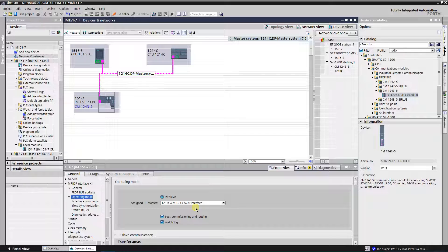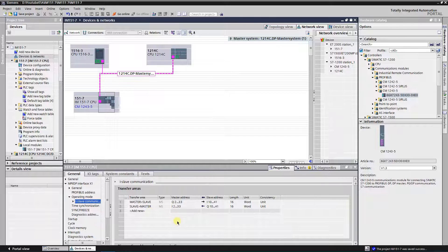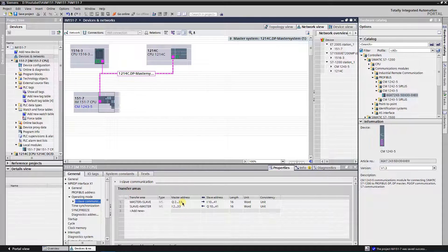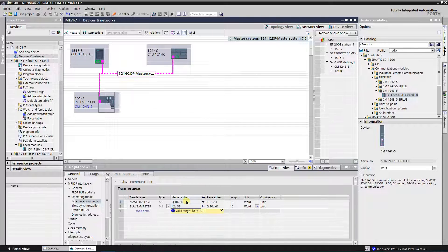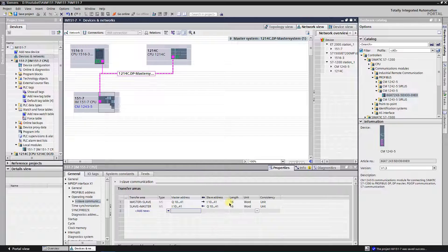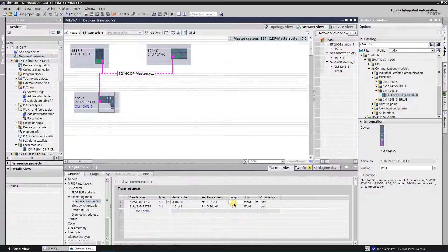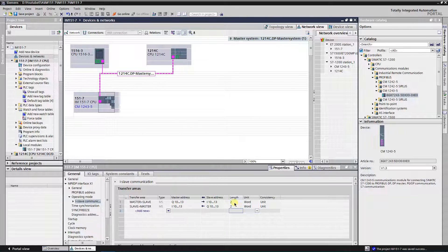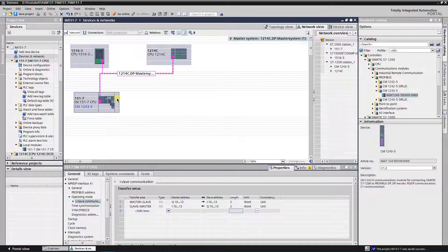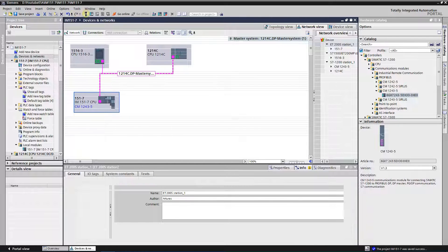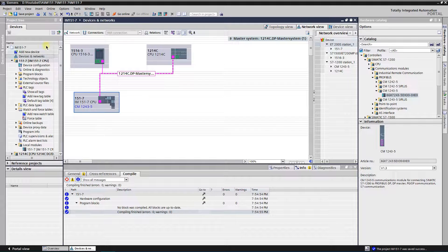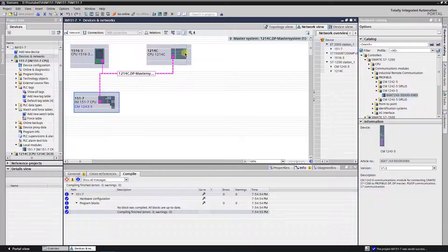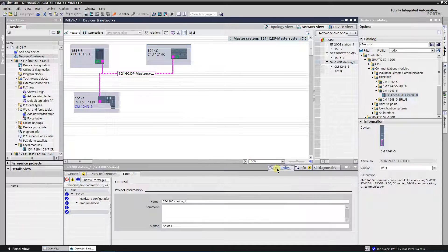Now, the transfer areas needs to be reconfigured. Select i slave communication. I will leave same addresses as for S7 1500 CPU, but I will reduce the length to two words. Configuration is finished. Now IM 151-7 CPU is an i slave for the S7 1200 CPU.